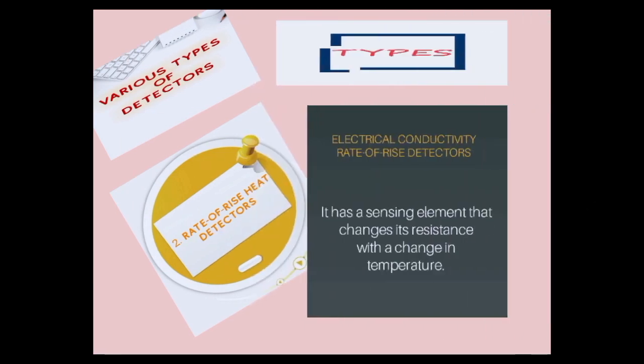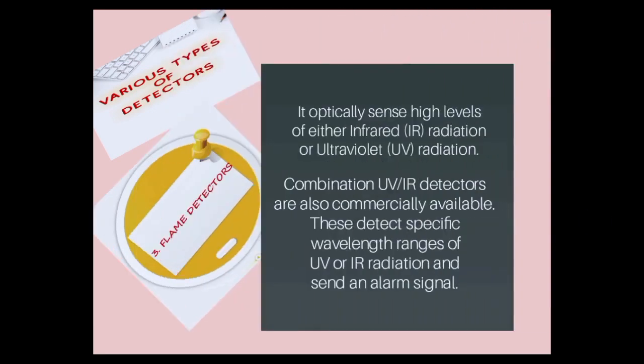We also have the electrical conductivity rate of rise detectors. It has a sensing element that changes its resistance with a change in temperature. The third type is the flame detectors. It optically senses high levels of either infrared radiation or ultraviolet radiation. Combinations of ultraviolet and infrared detectors are also commercially available. These detect specific wavelength ranges of ultraviolet or infrared radiation and send an alarm signal.